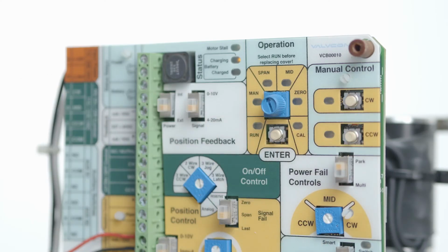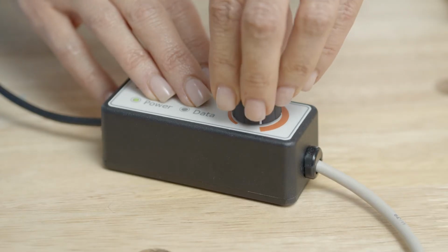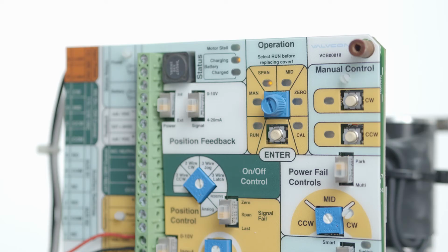If configuring for an on-off mode, a signal is not required. However, if using the analog or resistive control mode, apply the desired span position signal. Typically this will be 20 milliamps. Press the Enter button to save the span setting.